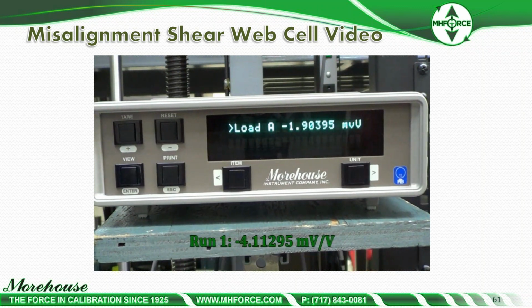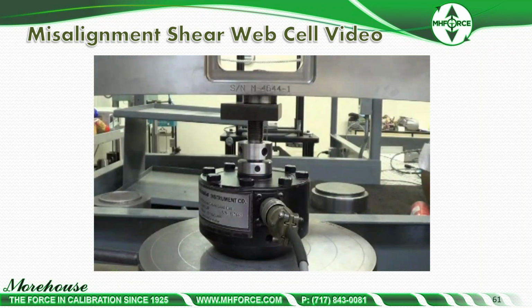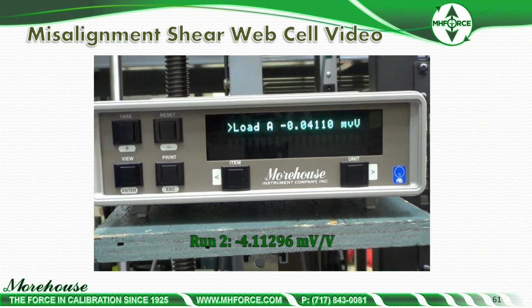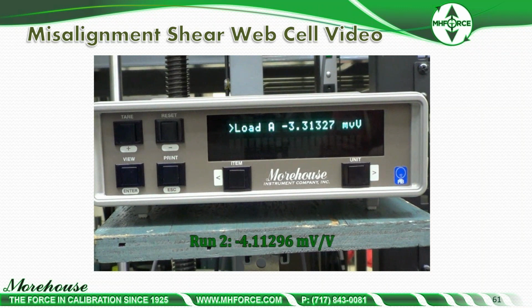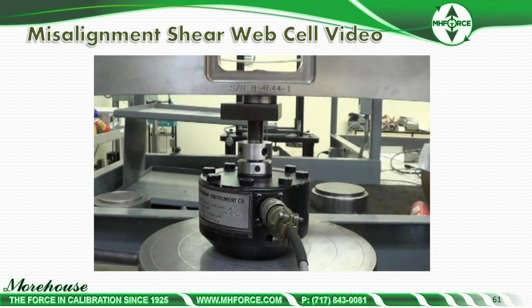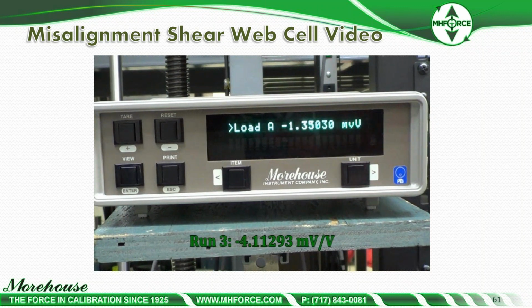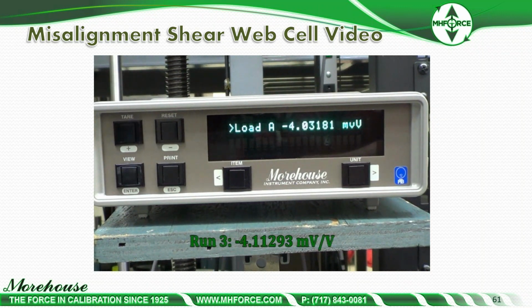So they should have tared this before it came down. That's a little bit backwards, but they tared it. I had an intern edit it, but they tared it, and then we're getting millivolt readings. You're going to get 3 sets of millivolt readings, and they're going to compare that really, really misaligned load cell with what we considered having pretty good alignment. And this is sped up. If you're paying attention, someone had a Penn State shirt on earlier, and now they have a different shirt on. But look at this.